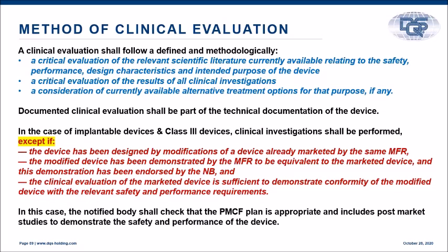So the method of clinical evaluation: a critical evaluation of relevant scientific literature currently available, critical evaluation of results of clinical investigation, consideration of currently available alternate treatment options for that purpose, if any. So you'll have to consider these things while you are preparing your clinical evaluation.